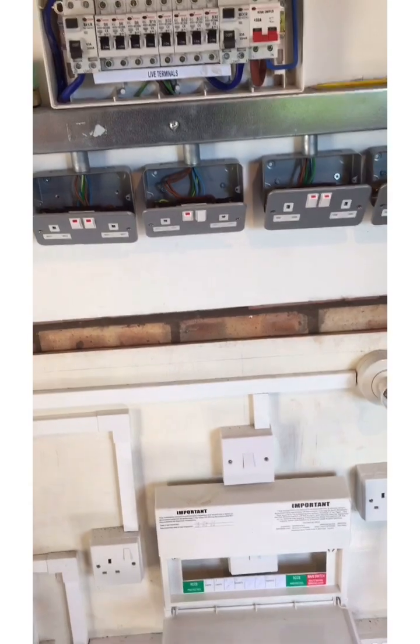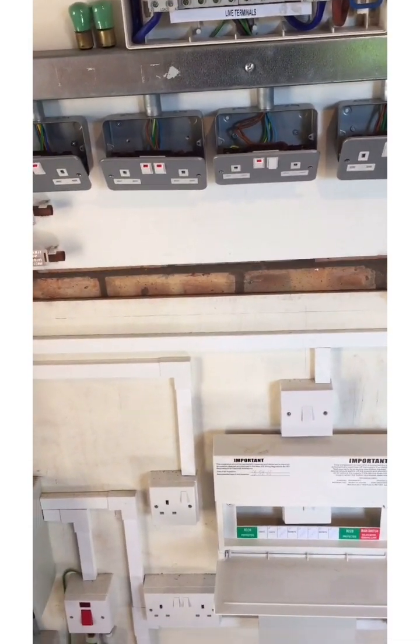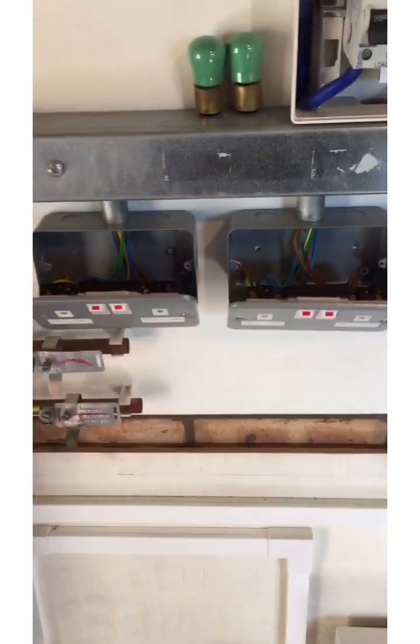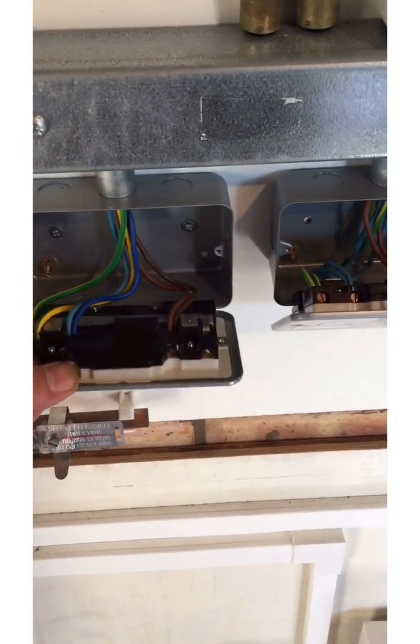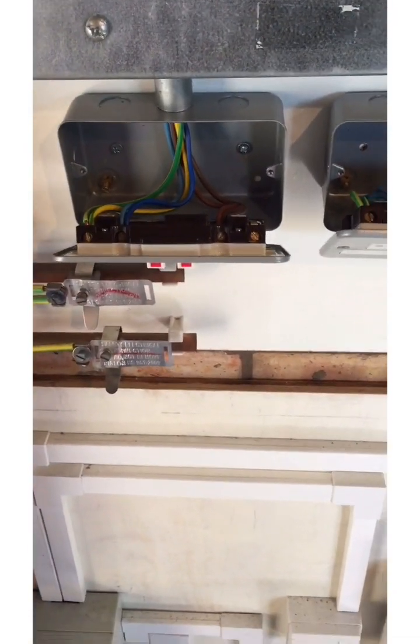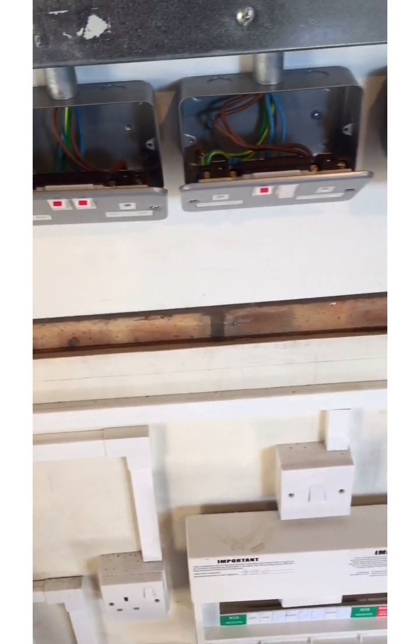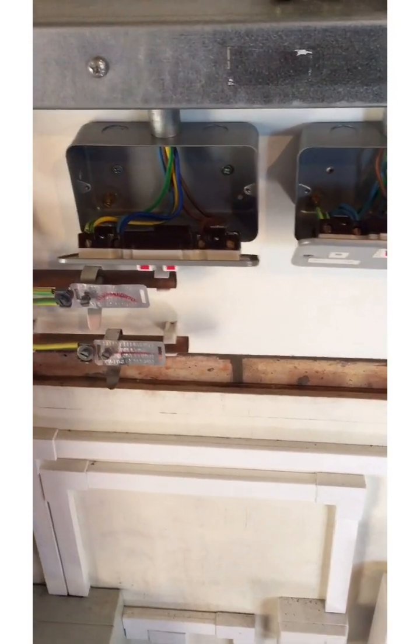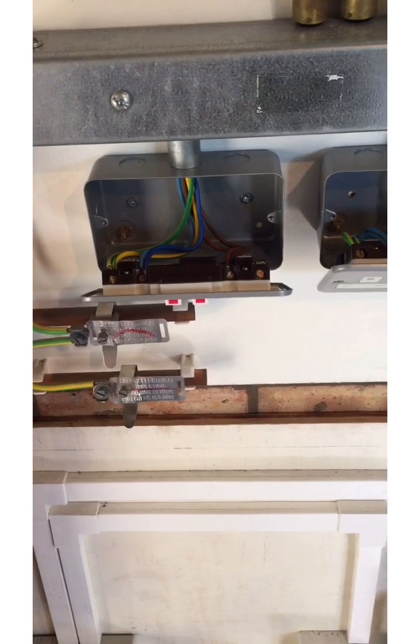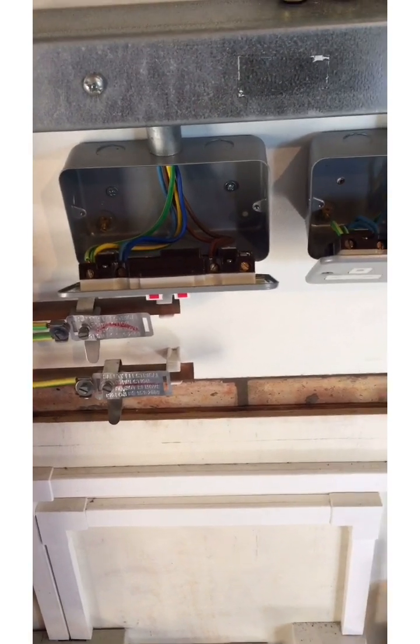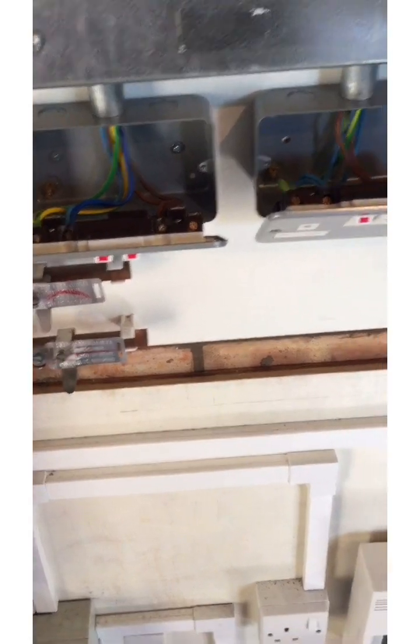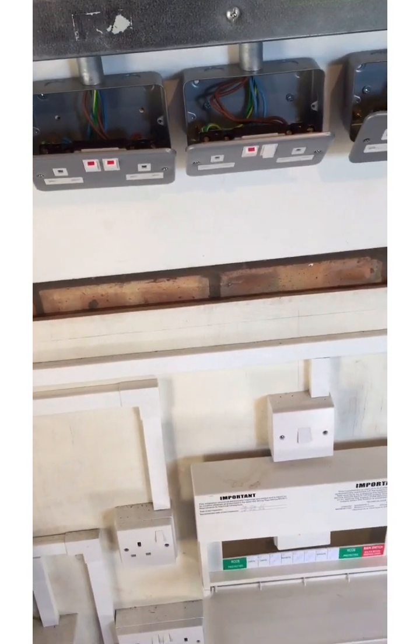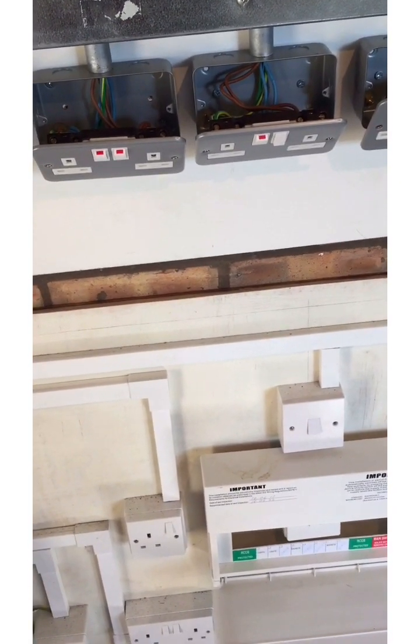If we go over to this particular board now the reason I didn't use that board there for this test is because again you don't have to have the socket faces removed normally but with this one if we wanted to do a ring test on this installation here we would have to remove these socket faces because if we've got them screwed back we get parallel paths through the sockets themselves and the trunking and that skews the value of the CPC.